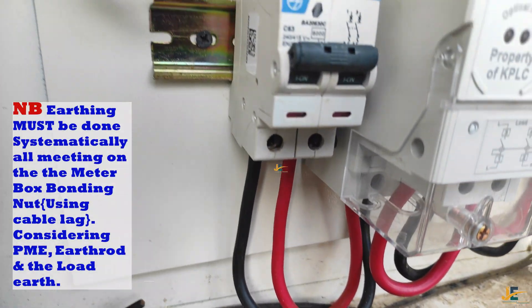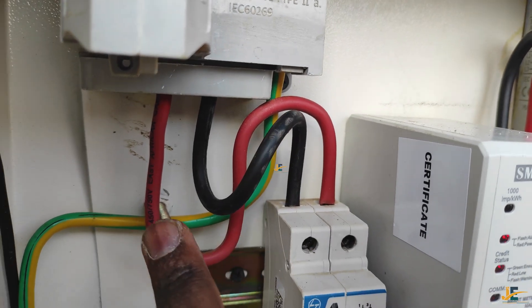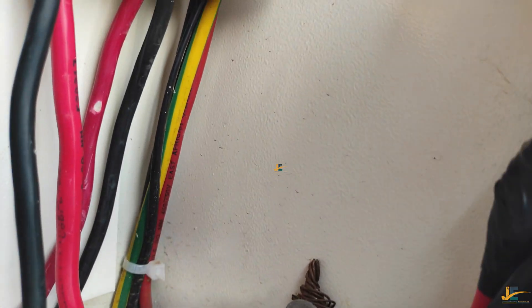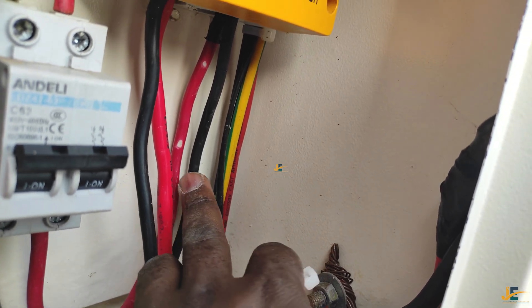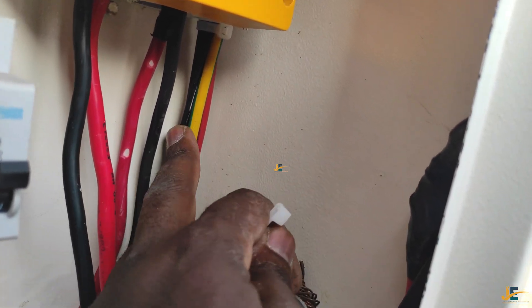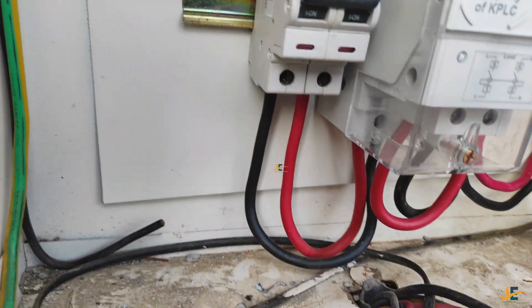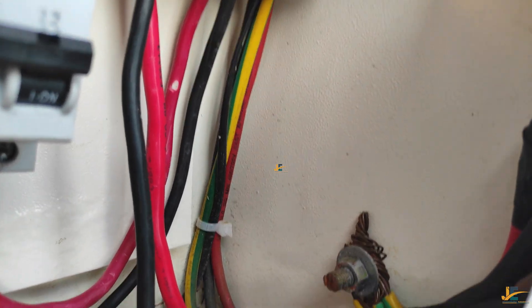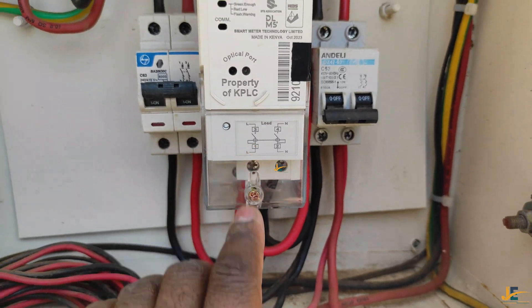A C63 MCB double pole will work very efficiently with the load this meter can accommodate. Regarding earthing — the earth must be done properly from the cutout, as you can see here. This is where we have a bonding point for the meter box. There is one earth coming from the PME and another earth going inside the house for the load. They should all meet at the bonding point.